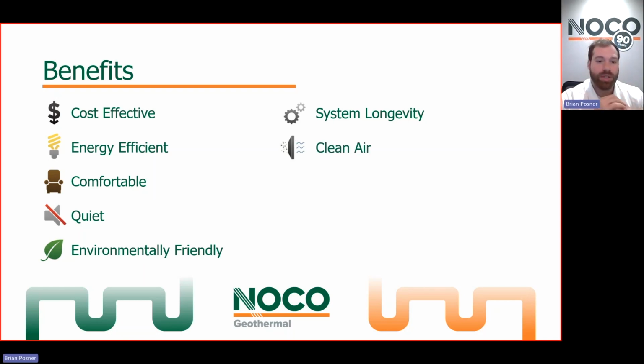Clean air. Geosystems typically have more active dehumidification than normal AC systems, and that's simply because the piece of metal that makes contact with the air to draw moisture out of it is a bigger piece of metal in geosystems. More surface area contact with the air means more dehumidification, but we also put in standard MERV 11 filters with Geo. That's one step below hospital grade air purification. And we do that just to put that extra level of cleanliness in your home. Now, that isn't to say you can't buy a MERV 11 filter for your normal furnace, but usually these filters are a little bit larger than what your normal furnace will allow. So the bigger filter capacity for Geo lets you use more industrial and more serious air filters that filter out a higher level of particulate matter.